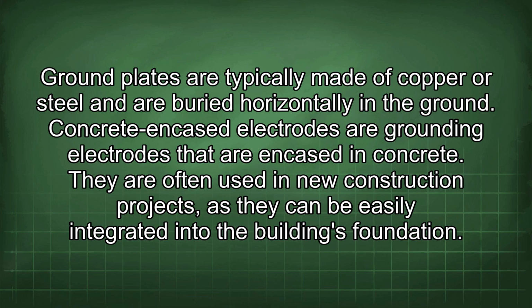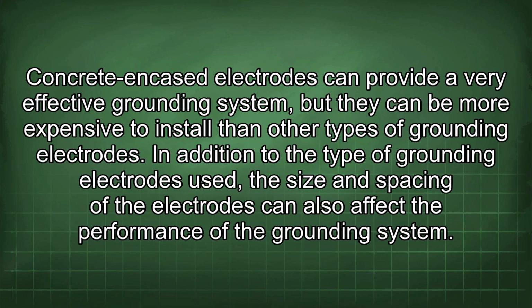Concrete encased electrodes are grounding electrodes that are encased in concrete. They are often used in new construction projects, as they can be easily integrated into the building's foundation. Concrete encased electrodes can provide a very effective grounding system, but they can be more expensive to install than other types of grounding electrodes.